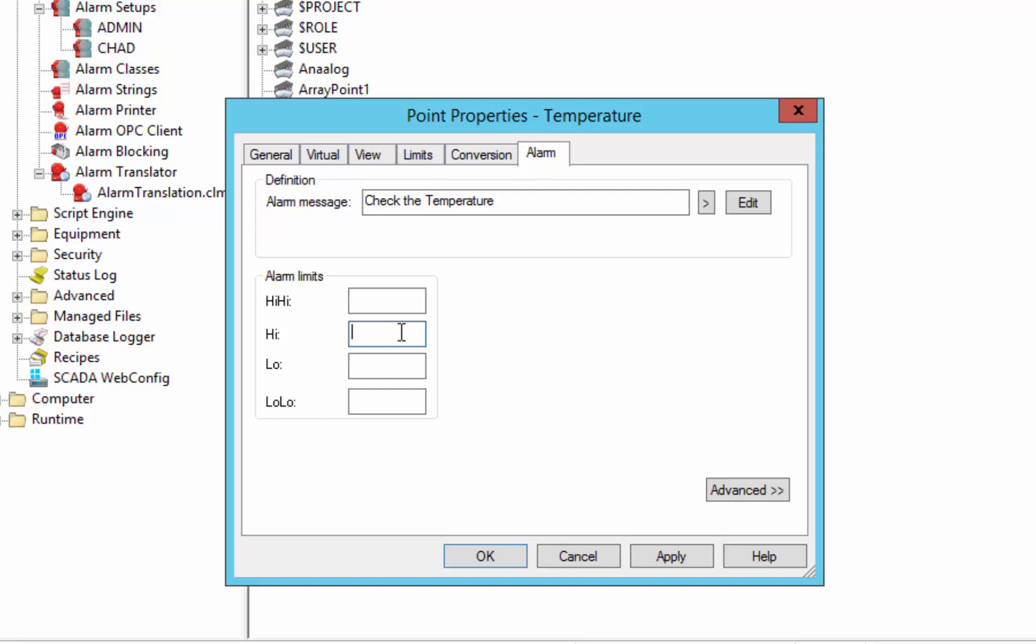So if normal operating temperature is 15, we may want to say that when the temperature gets above 30 degrees Celsius, it's getting too hot. And if it gets above 35 degrees Celsius, that's way too hot. So give that a high, high alarm.